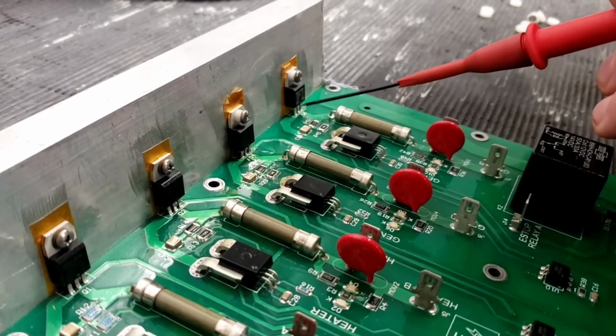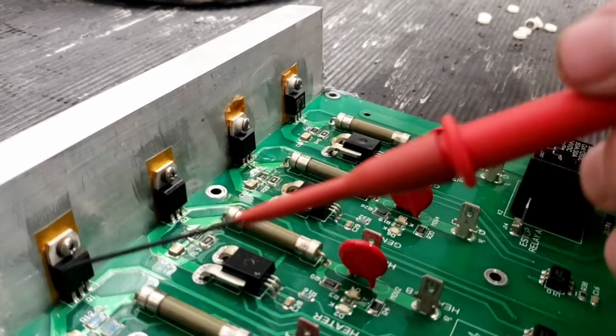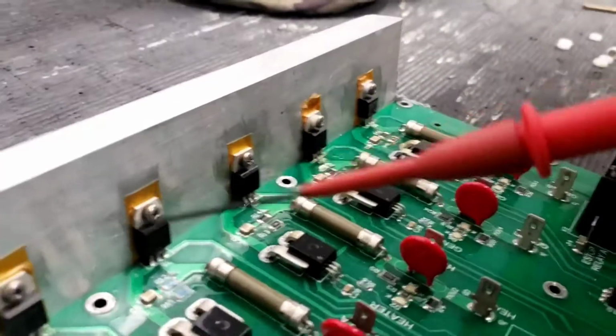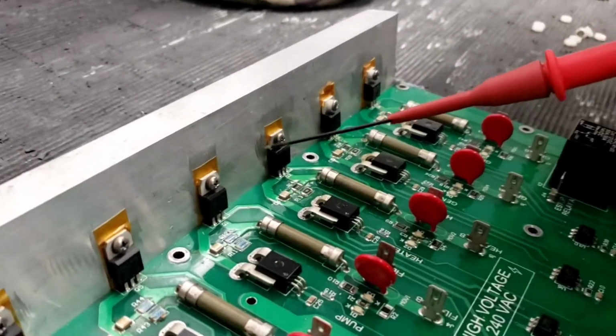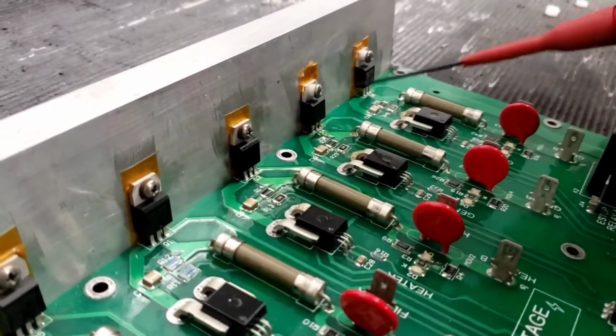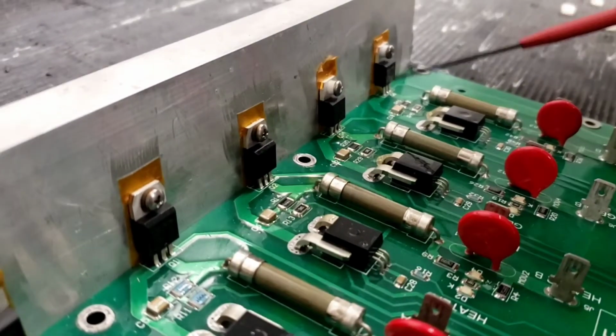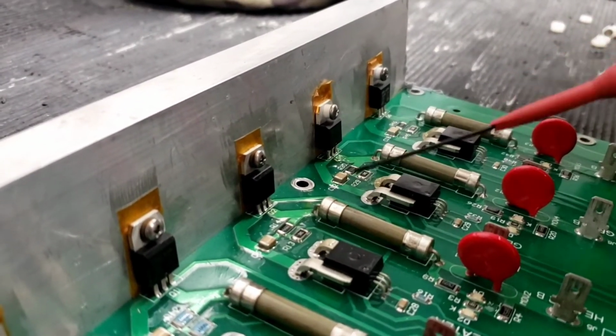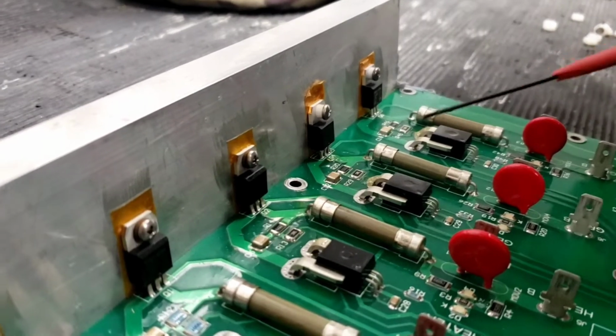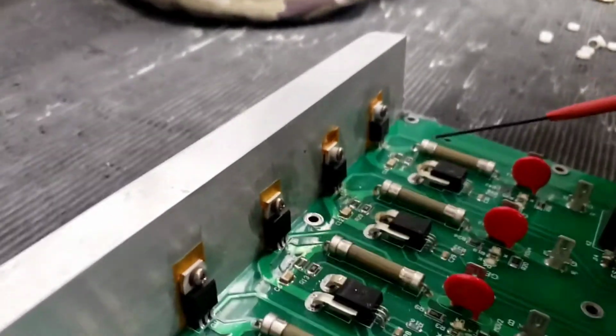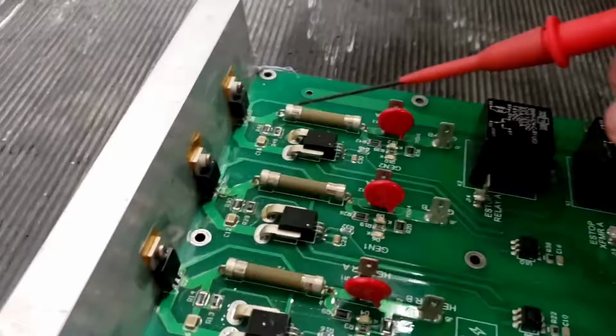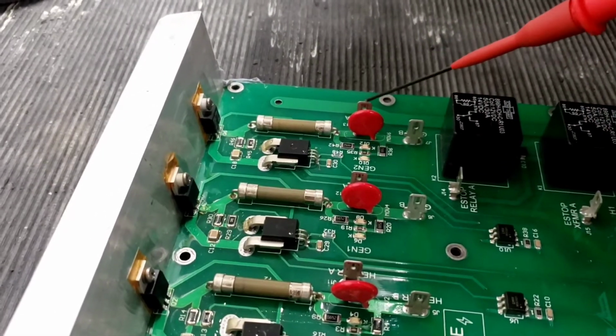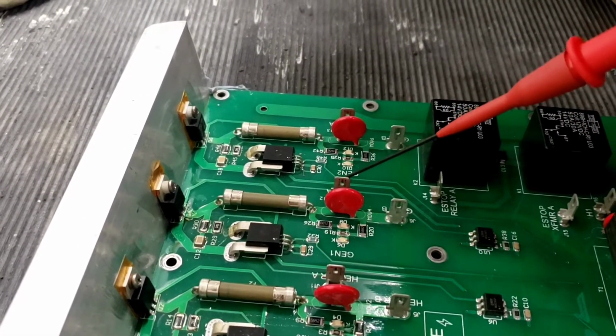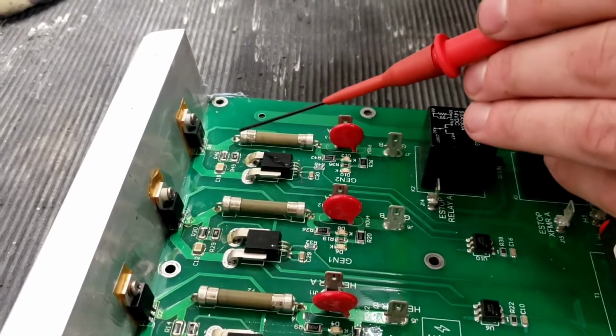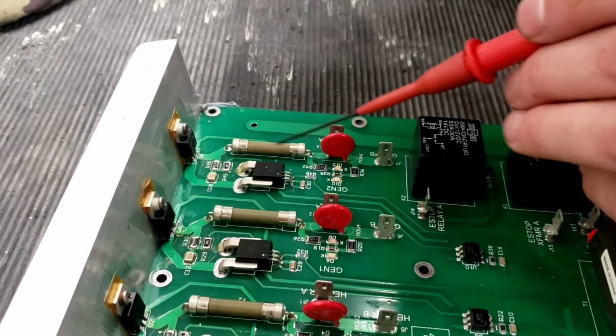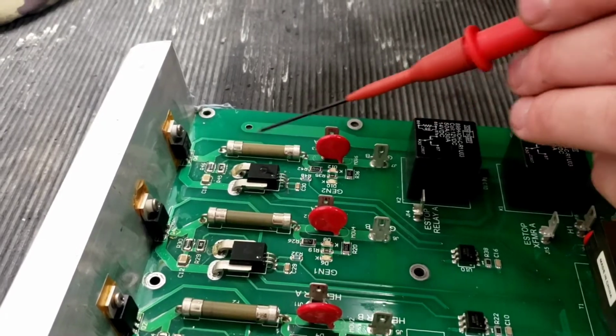So we replaced this transistor and this one with the same exact part number, because in the past we've had some issues with these transistors. So we know that's all good. We checked these capacitors, these resistors, the fuse, and all this stuff checked good separately and through the whole circuit, from good to suspected bad. We also had 120 AC on this leg and 120 AC on this leg, which gets your 240. We know these fuses are good because we checked continuity, and there's 120 on both sides of the fuse, so we know the circuit's good.